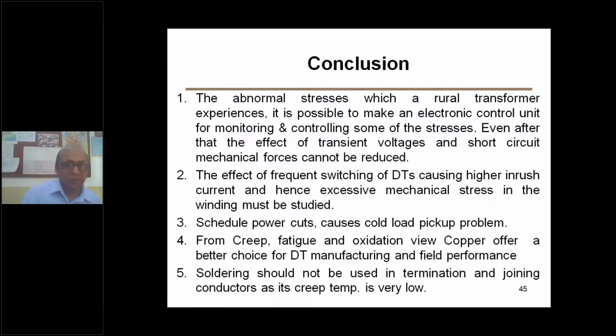Various kinds of transients and short circuits appearing in the rural area are also very common, and that must be taken into account in making the transformer. Whenever you have such problems, you are also associated with another problem, inrush current. When switching on the transformer, there are chances of inrush current, and this inrush current is equivalent to a short circuit. So let us say 10 or 20 times of switching on the transformer is equivalent to one short circuit, something like that. Therefore, this higher inrush current occurs because you are switching on the transformer many times in a year or a day, and that must be avoided.